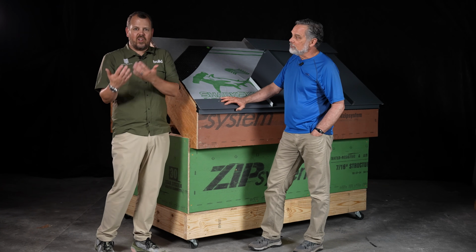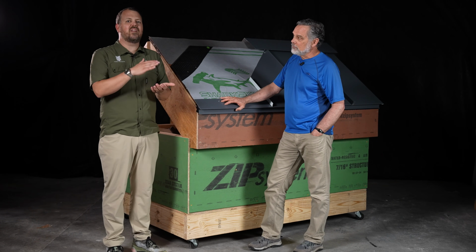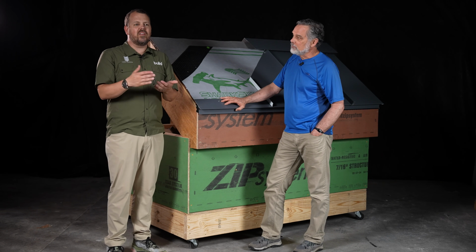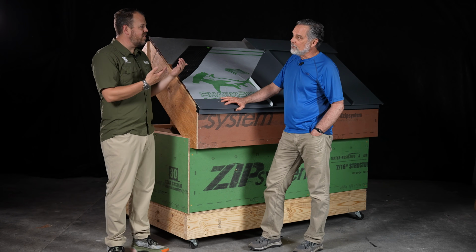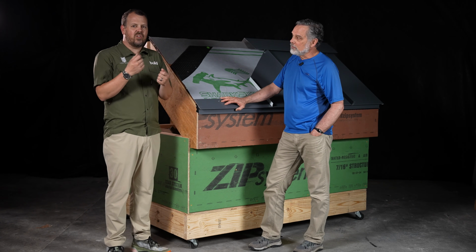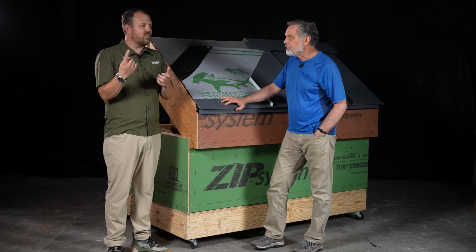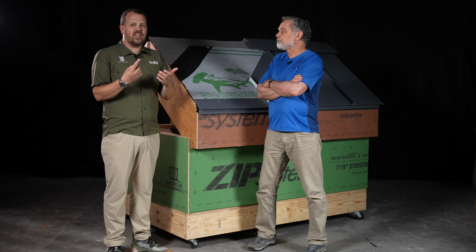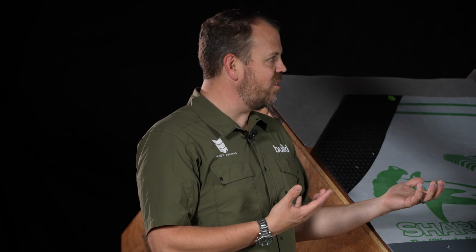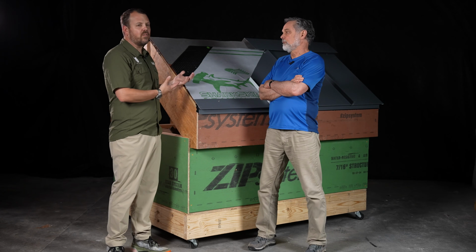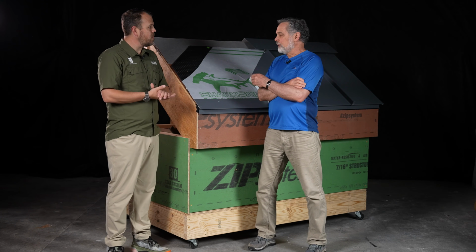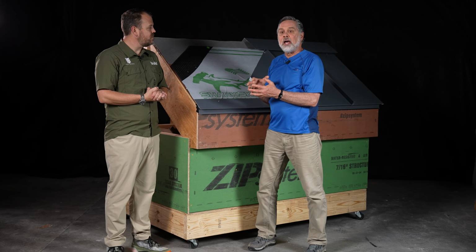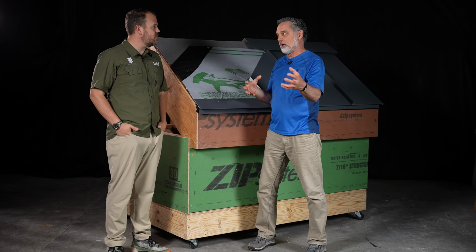We have a code that is incredibly complicated, is incredibly dense, and there is a lot to it. But I think that it's really interesting that we just took one section, really, 805.6, and said, let's do a deep dive, and then let's apply, well, if I were going to do this at my own home, or if I lived in climate zone 1 to 3, what would it look like if I were doing it for myself? And here it is.